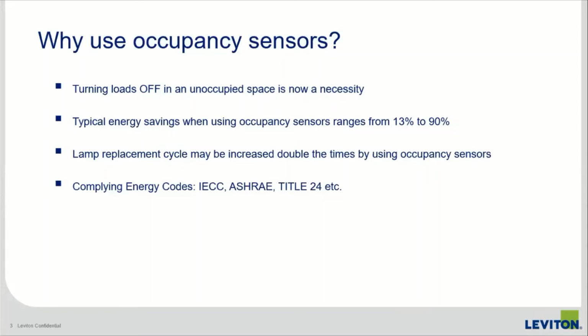A lamp or LED light fitting replacement cycle may be increased to double the time. For example, the lifetime of an LED is either 30,000 hours or 50,000 burning hours. By using an occupancy sensor and setting the right off delay time, that's very important, because if your off delay time is very short, for example, if the light turns off every 30 seconds or every 1 minute, the ballast life will decrease. So by setting the right off delay time, the lifetime of an LED or a lamp can be doubled. For example, if an LED is set to work for 4 years, it may work for 6 to 8 years.